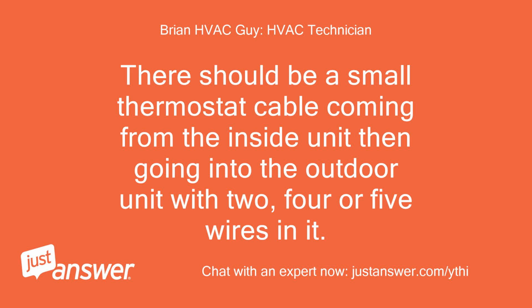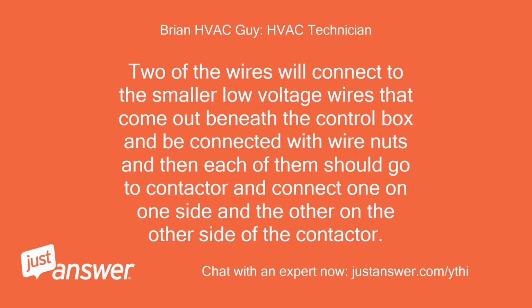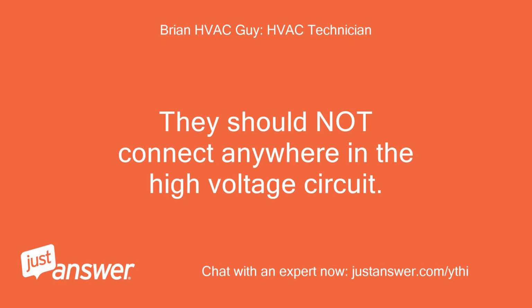There should be a small thermostat cable coming from the inside unit then going into the outdoor unit with 2, 4 or 5 wires in it. 2 of the wires will connect to the smaller low voltage wires that come out beneath the control box and be connected with wire nuts, and then each of them should go to the contactor and connect one on one side and the other on the other side of the contactor. They should not connect anywhere in the high voltage circuit.